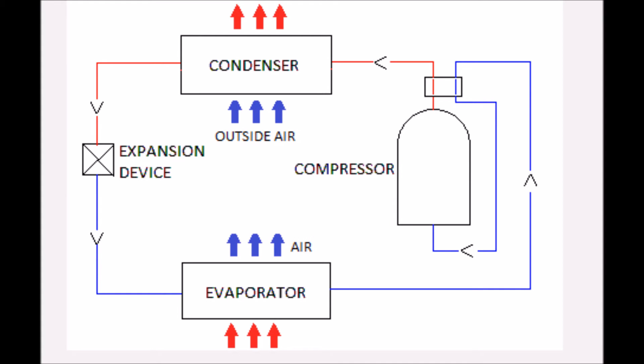Figure 1.4 shows how the heat pump works. Compressor is compressed low pressure low temperature gas to high pressure high temperature superheated vapor. Vapor flows into heat exchanger that allows high temperature refrigerant to reject heat causing the refrigerant to condense into saturated liquid. Liquid moves across an expansion device into a second heat exchanger. In the evaporator inside heat exchanger heat is absorbed by the refrigerant causing the liquid to boil off to a completely vaporized state and last the process starts all over again.